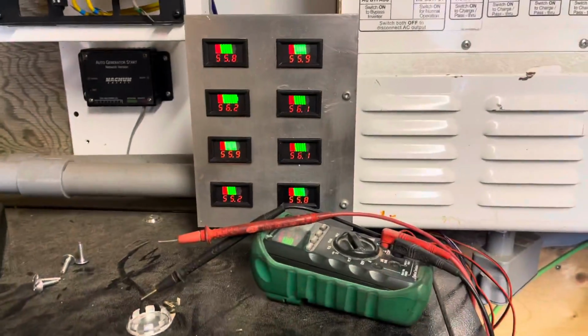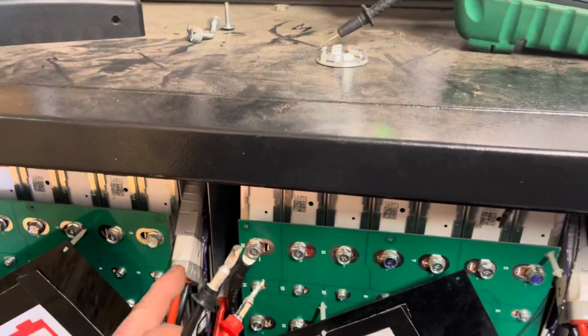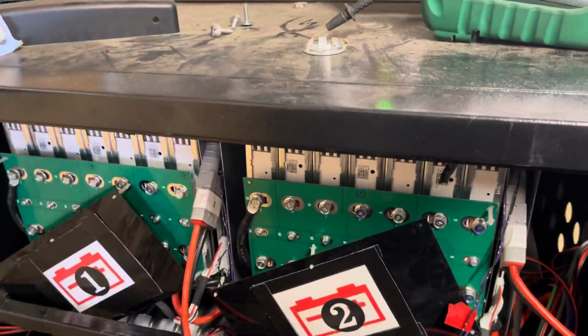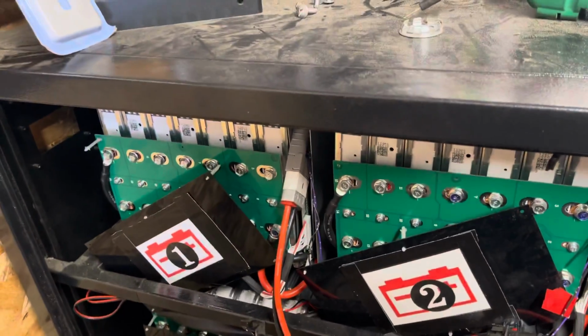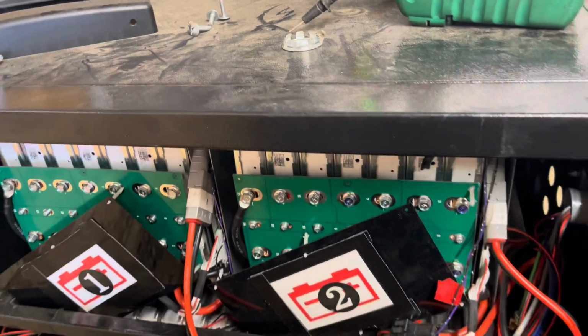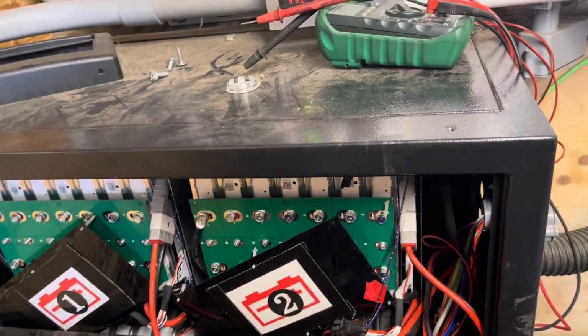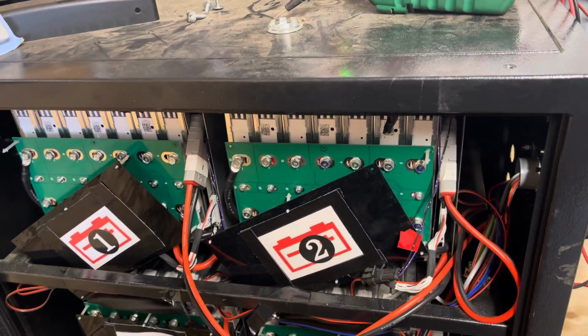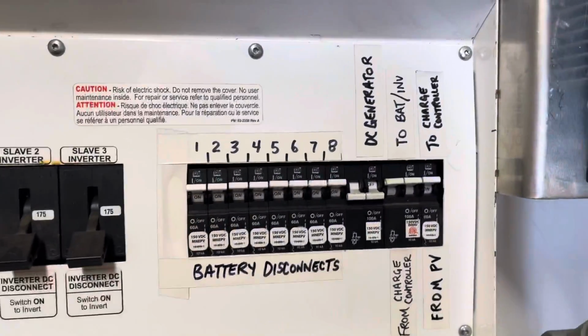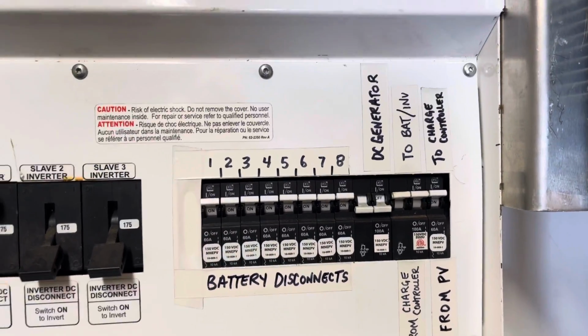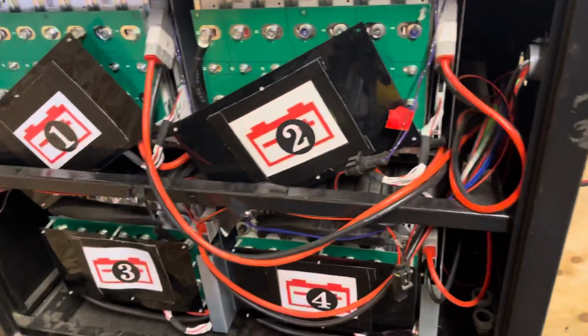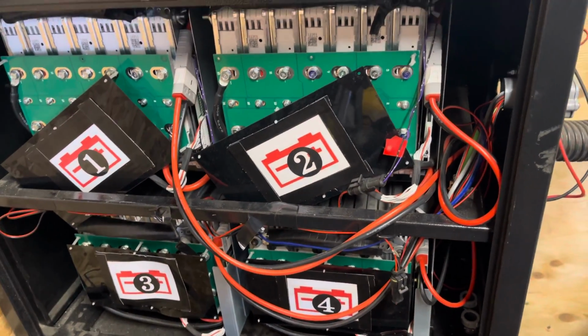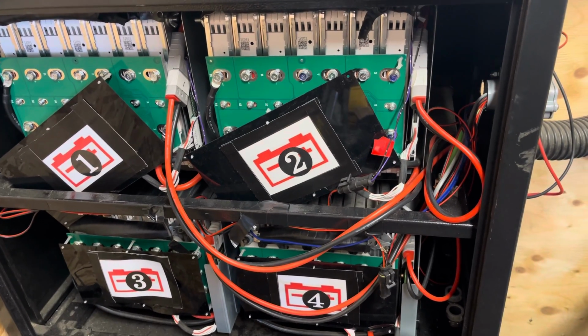At that point, I reconnected my feed - disconnected that piece, reconnected this back in, which had everything connected back to the bus bar. At that point I could turn on the rest of them, because they would back feed onto each BMS, allowing it to receive a charge.